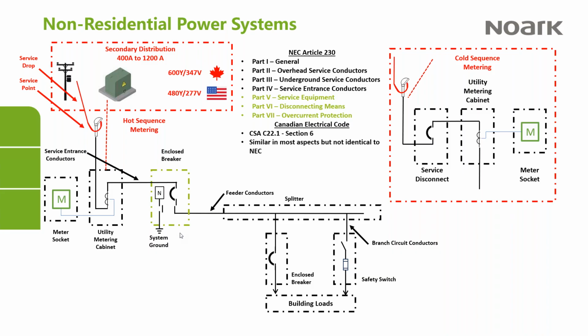When this enclosed breaker is being used for service entrance, the system ground conductor, so that's the wire that comes from that ground rod, must be connected to the neutral. And in order to ensure that the neutral is grounded at that point and only at that point, that's where the bonding conductor comes in that bonds the neutral to the ground. In non-service entrance applications, you remove that bonding jumper or bonding screw in order to ensure that the neutral is only bonded in the one place in the service entrance box.